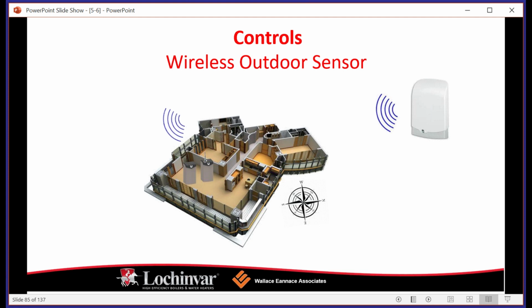Now, having said that, the sensor that we use that's sent in with the kit when you get your boilers is a wired sensor, right? You're going to run like an 18-3 bell wire back to the boiler and land it at the low voltage terminal strip and tell the boiler what the outdoor temperature sensor is. The outdoor air temperature sensor should not be mounted anywhere but the north side of your structure, right? Typically not in direct sunlight, because that's going to kind of give a false reading. It's going to tell the boiler that it's hotter or colder than it really is.